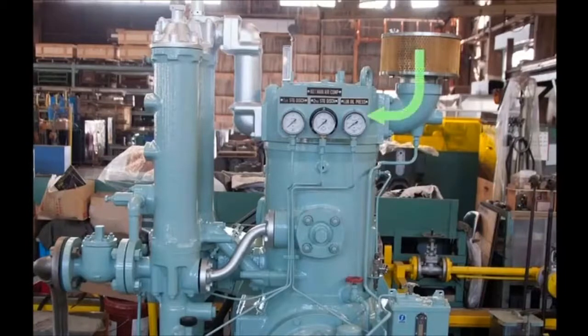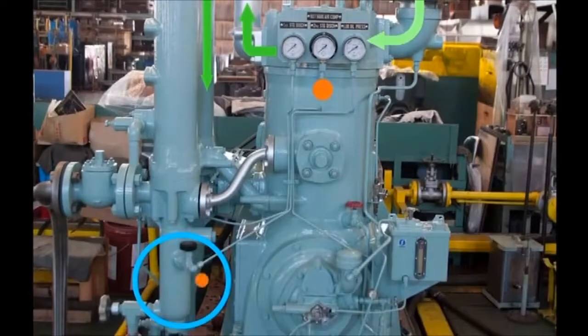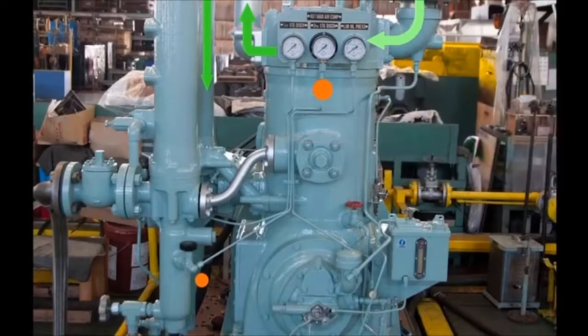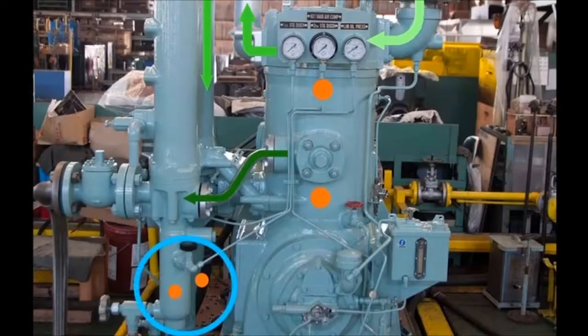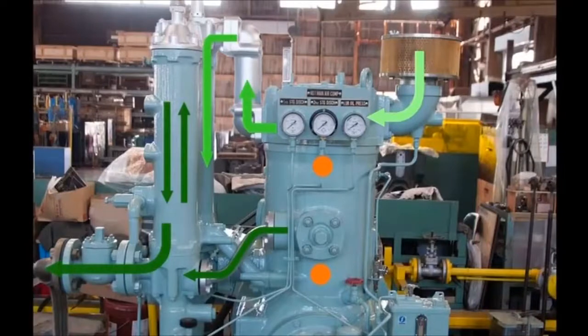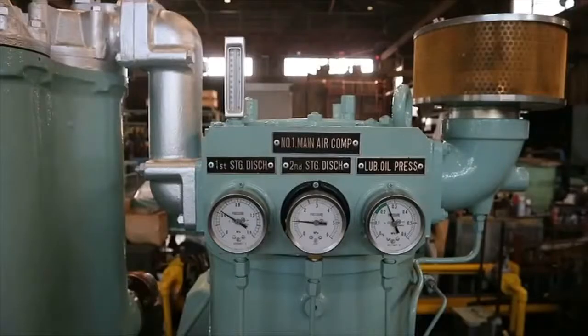Air flows from the suction filter via the low-pressure suction valve to the upper part of the cylinder, where it undergoes compression. It goes from the low-pressure discharge valve to the intercooler, with drainage removed in its lower part. After going through the high-pressure suction valve, the air is drawn into the cylinder in the lower part of the high-pressure piston for compression, and via the high-pressure discharge valve to the aftercooler. Drainage is removed in the drain separator in the lower part of the aftercooler, and the air goes via a check valve to be finally fed into the air tank.